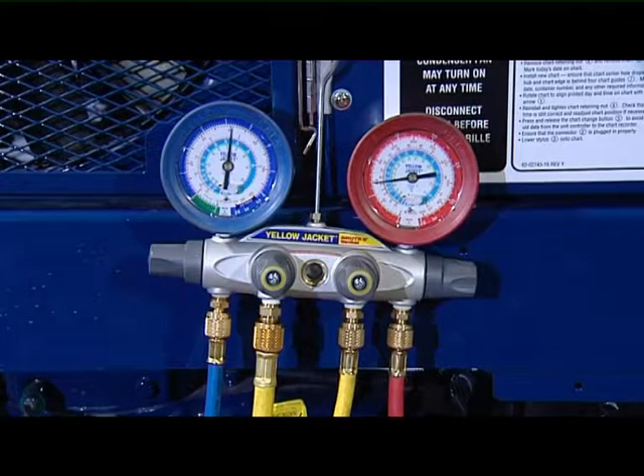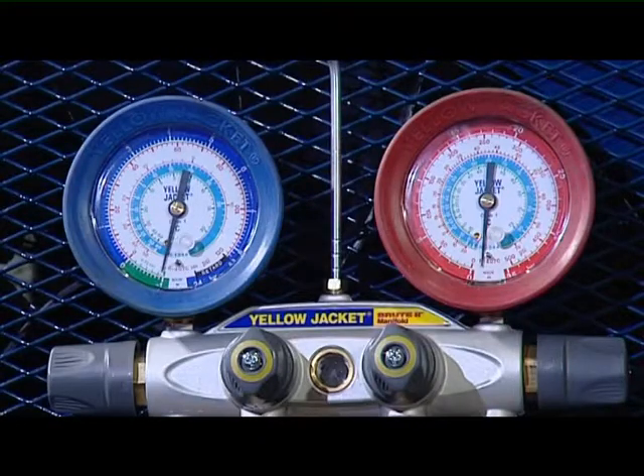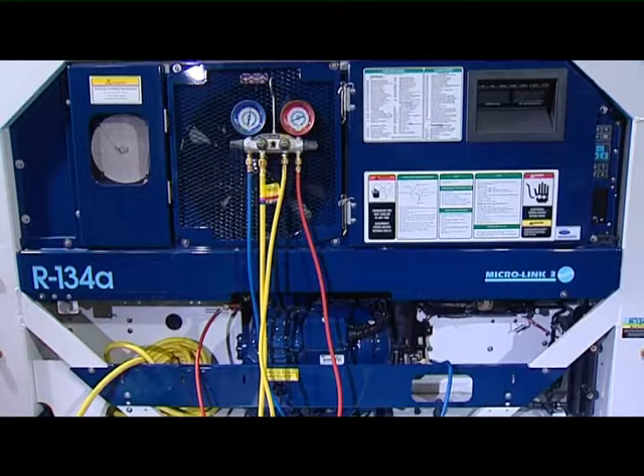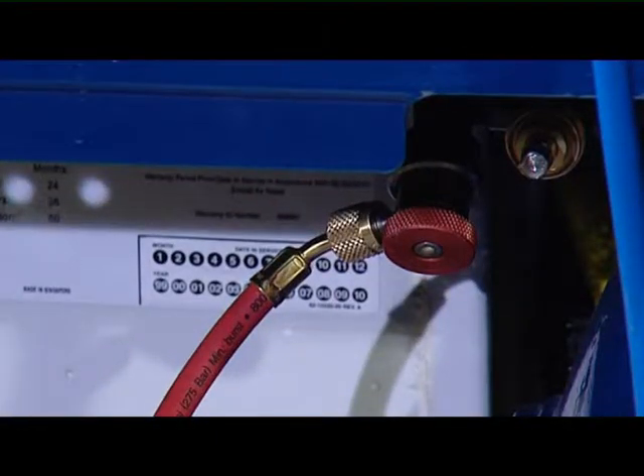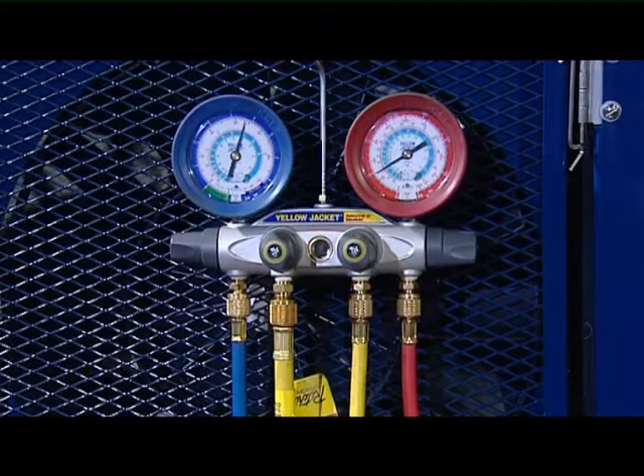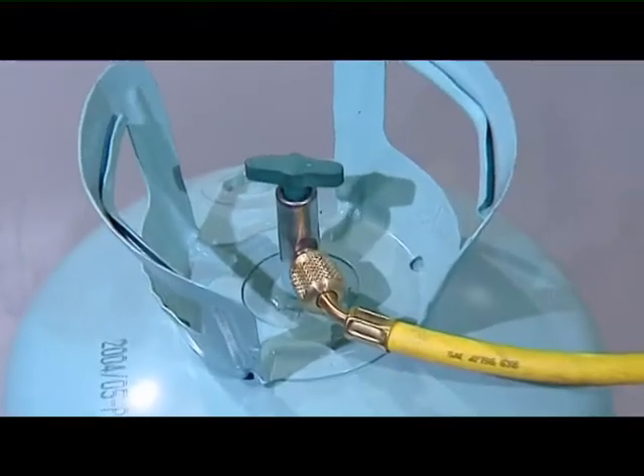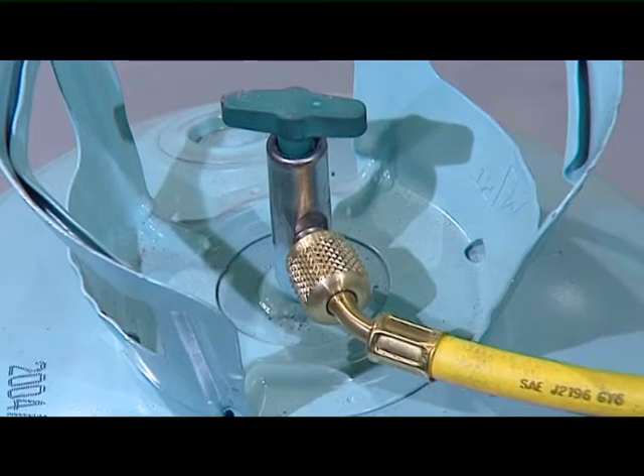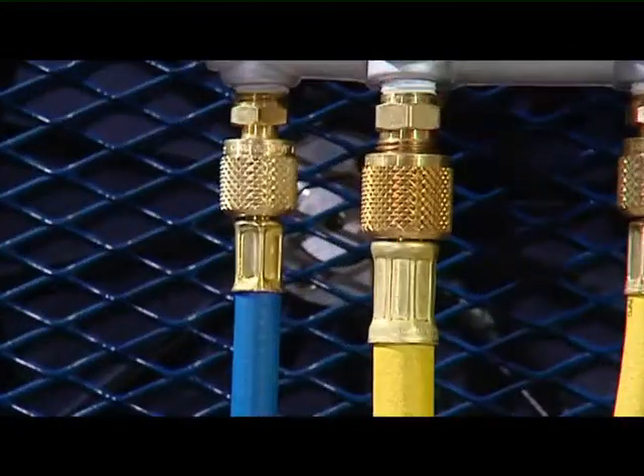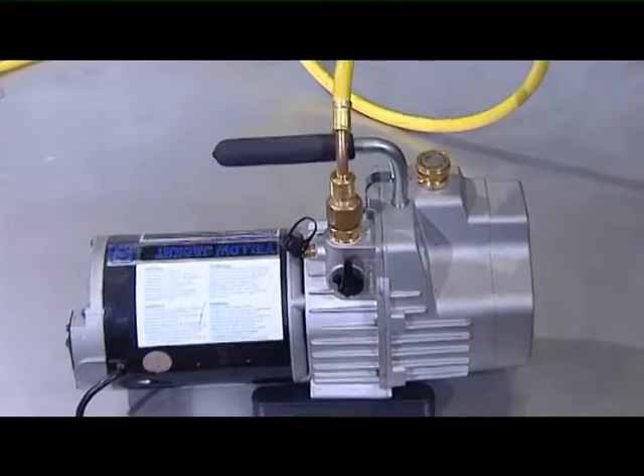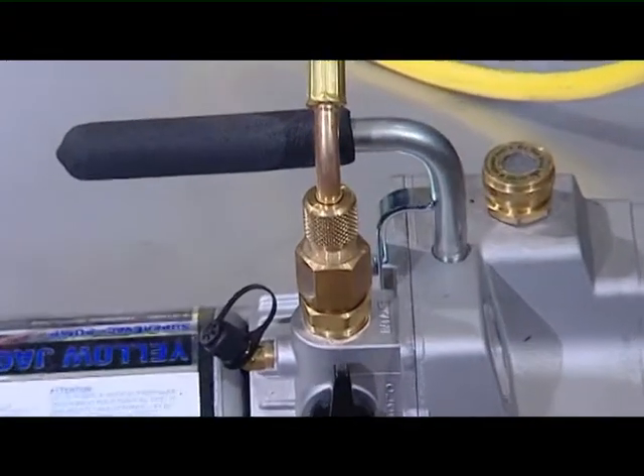The manifold gauge set consists of a low side gauge, a high side gauge, and 4 hoses. The low side blue gauge reads pressure or vacuum, and the high red side gauge reads pressure only. There is a red hose for the high side, a blue hose for the low side, a yellow hose for connection to a refrigerant cylinder for charging refrigerant to the system, and the second yellow hose, a larger size, for connecting to a vacuum pump when evacuating.